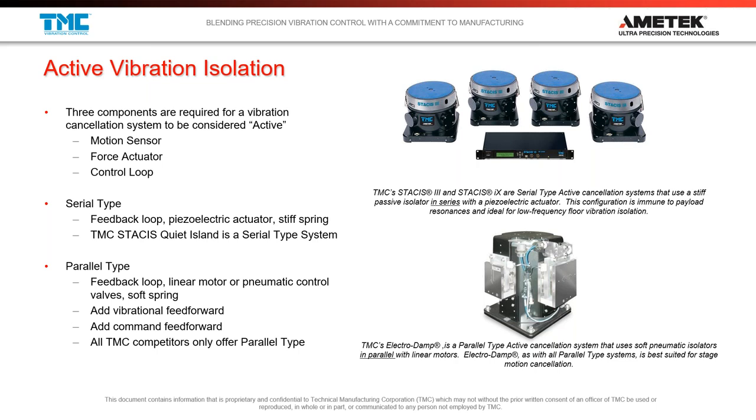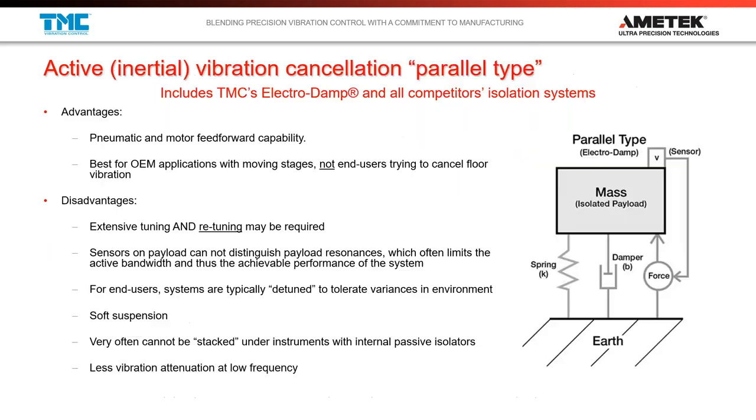Now, parallel type systems, they work really well. You can add vibrational feed forward, you can add command feed forward. And just as a note, parallel type is offered by basically every company in the world for floor vibration control, but serial type is unique to TMC for floor vibration control. But as I'll talk about in later slides, there's reasons why you want to use serial type for floor vibration control and why it might not be suitable for motion control and vice versa. You want to use parallel type mostly for motion control, like stage motion control, but it might not be suitable for floor vibration control.